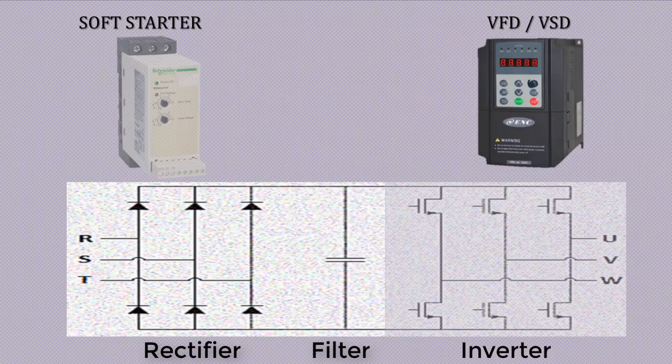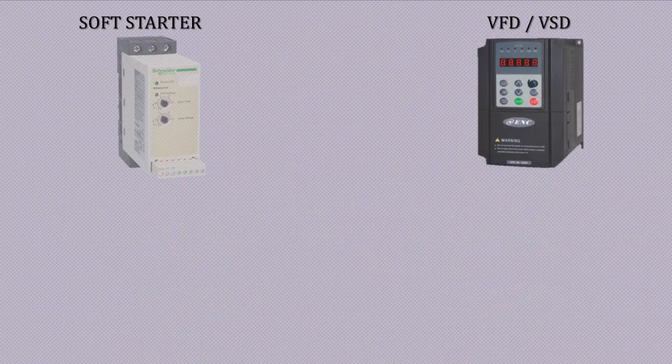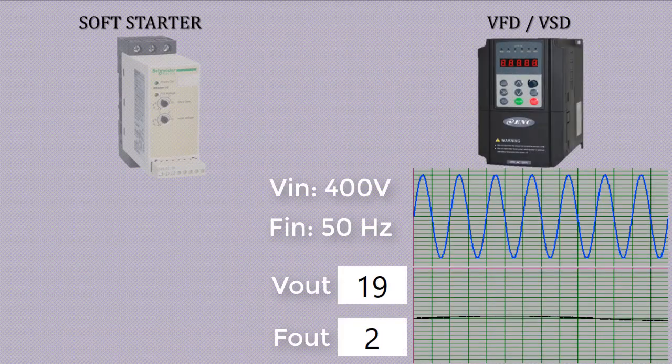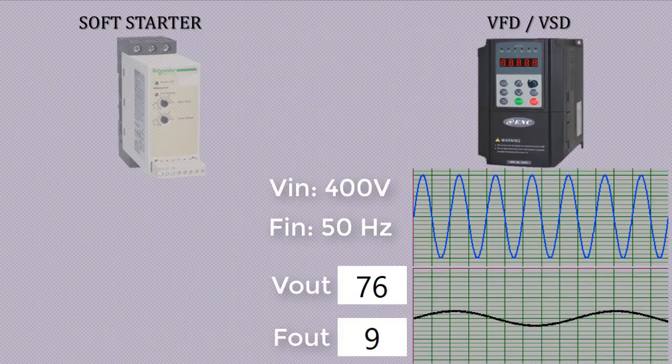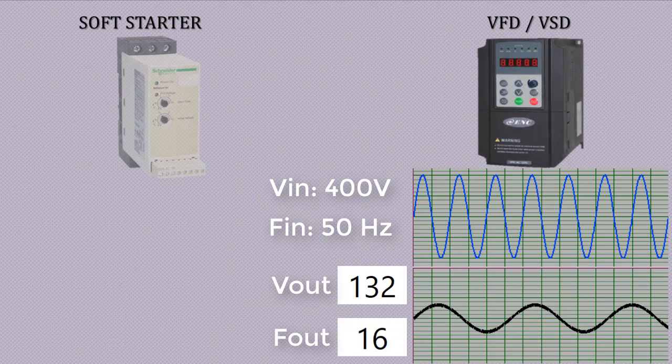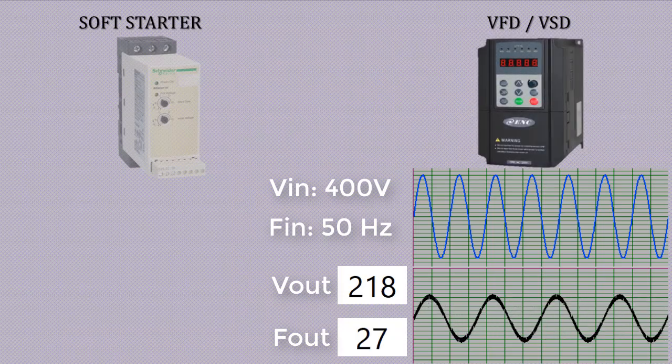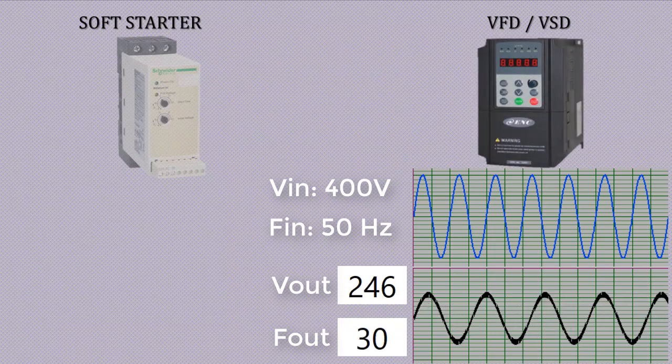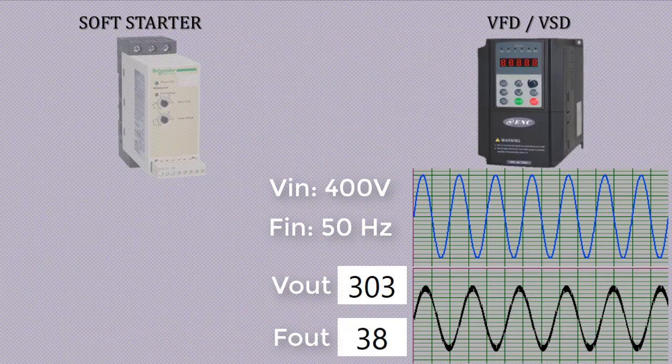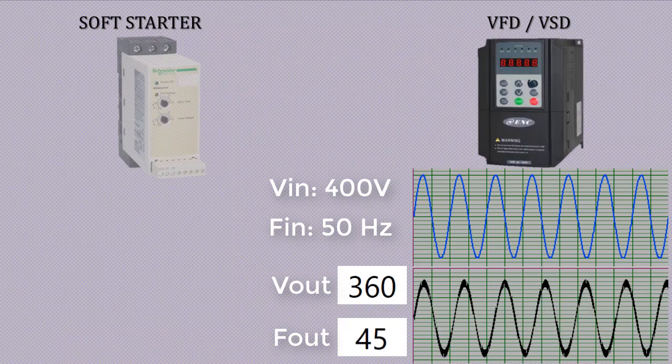If we set acceleration time 12 seconds and set frequency 50 hertz in VFD and initiate start command, then output frequency is increased from 0 to 50 hertz and output voltages are increased from 0 to rated voltage in 12 seconds by varying the firing angle across IGBTs, which is clear from its waveform.